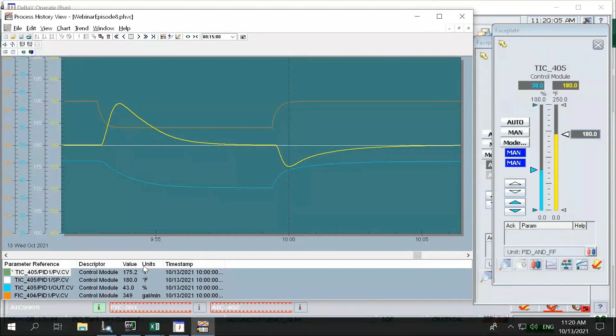Now, there can be some pitfalls with the feed forward calculation. Ideally, in theory, the actual feed forward gain should have been around 1.25. However, this process is actually a bit nonlinear, the process gain changes based on the flow rate, so it's not super linear, and let's face it, there are really no true linear processes out there. If I had put in the true theoretical feed forward gain, you'd see an overcorrection, because now you have two controllers fixing the same problem, and it overcorrected. That's what we need to be careful of: whatever theoretical feed forward gain you calculate, we need to back off a little bit.